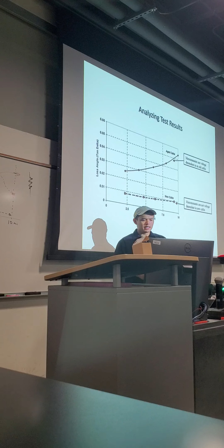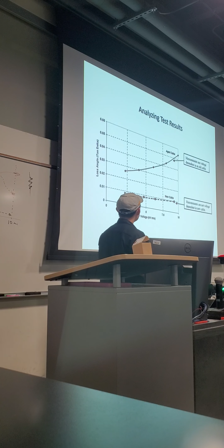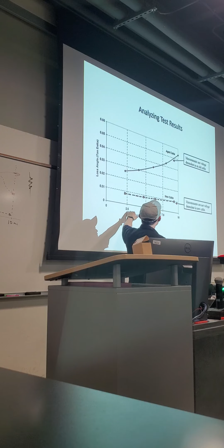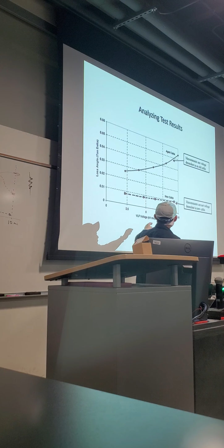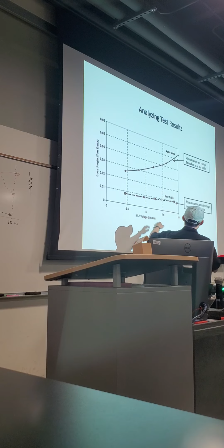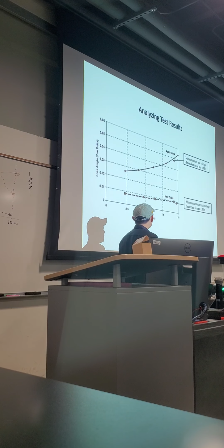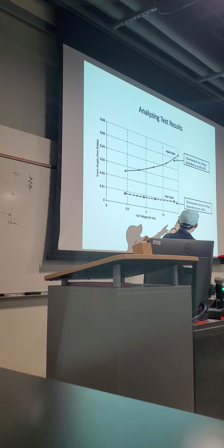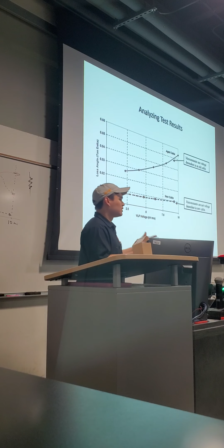Now the way these will work is you'll actually step up the voltage at increments. First you'll do 2.5 kV and see how the capacitive and resistive components interact. Then you'll set it to 5 kV, and again you'll see how the capacitance and the resistance interact. Eventually you'll hit your maximum value, which is dictated by NETA MTS. But new cable, what do you notice about new cable?